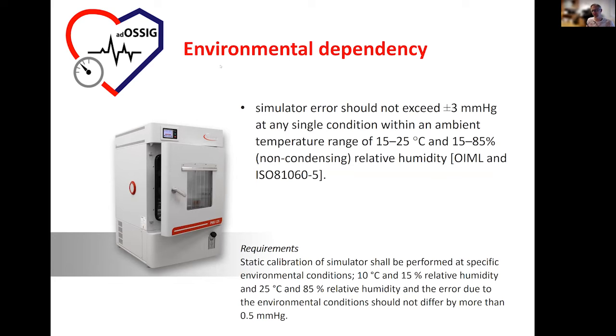The last test would be environmental dependency. This is done in climatic chambers. Climatic chambers are boxes where you can control temperature and humidity. Temperature usually from like -50 to 200, and humidity from 0 to almost 100, non-condensing. Anyway, we decided, also based on some technical specifications and some ISO standards and OIML, the international legal metrology organization, which also has some recommendations for blood pressure monitors. And this is the classical range where a simulator should function properly: around room temperature, from 15 to 25 degrees and from 15 to 85% relative humidity, non-condensing, of course.